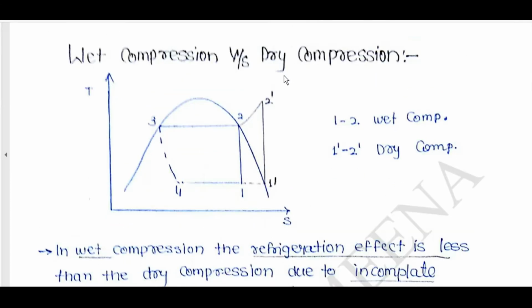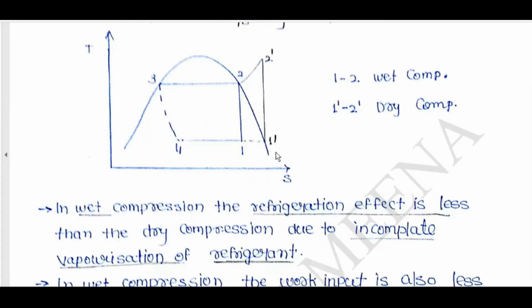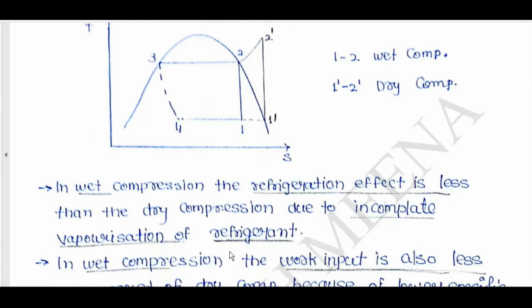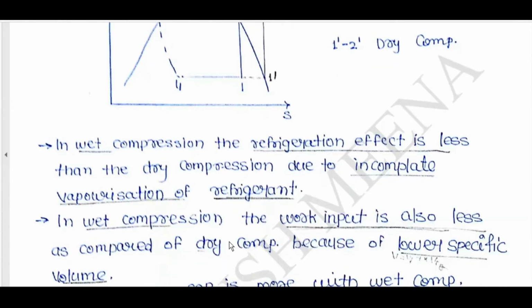Wet compression versus dry compression. 1 to 2 is wet compression, as 1 is in the wet region. 1 prime to 2 prime is dry compression. In wet compression, the refrigeration effect is less than in dry compression due to incomplete vaporization of the refrigerant. In wet compression, work input is also less as compared to dry compression because of less specific volume.